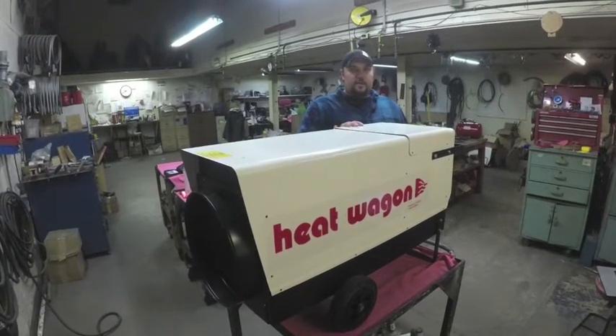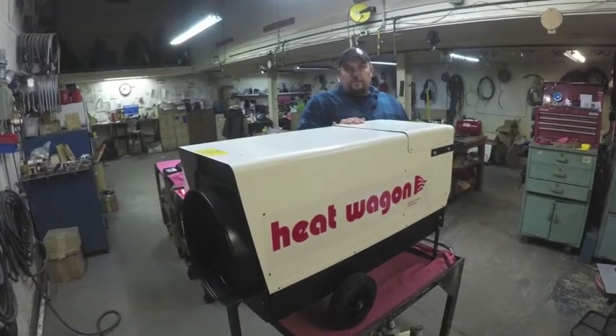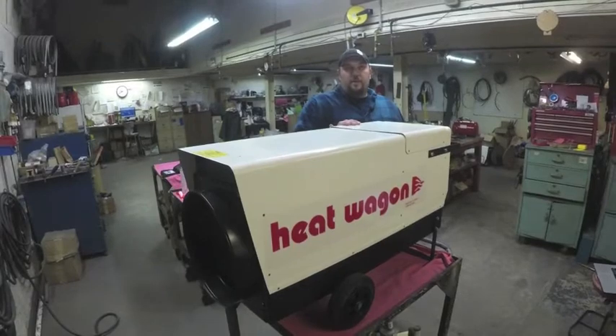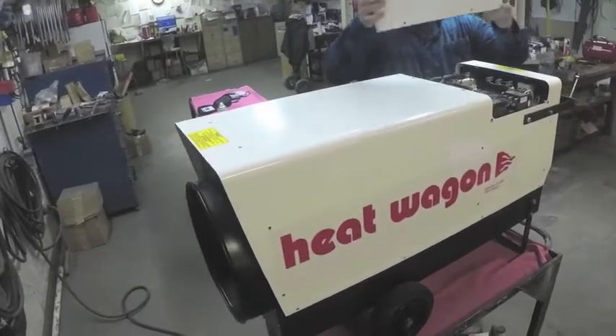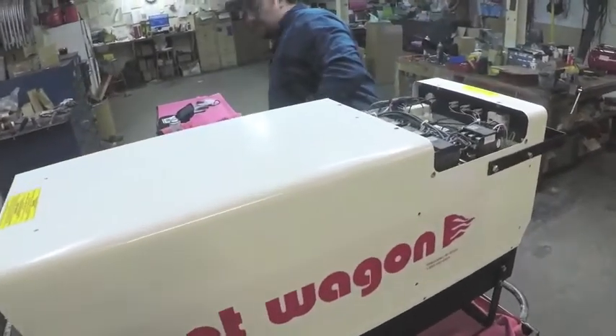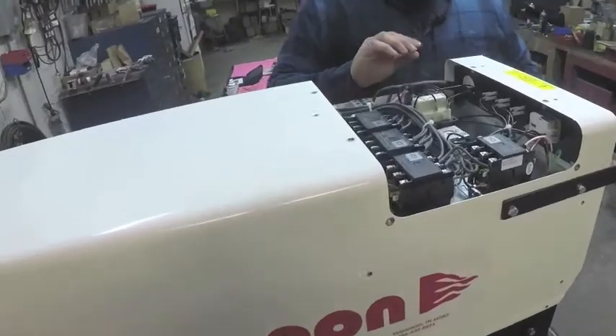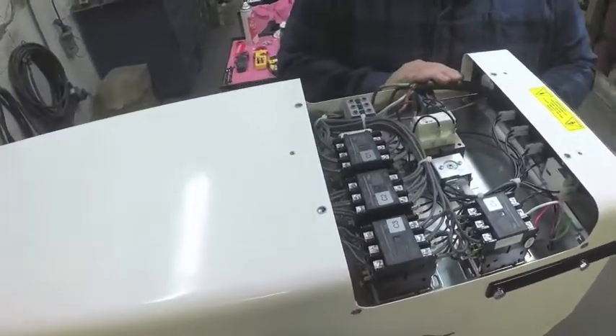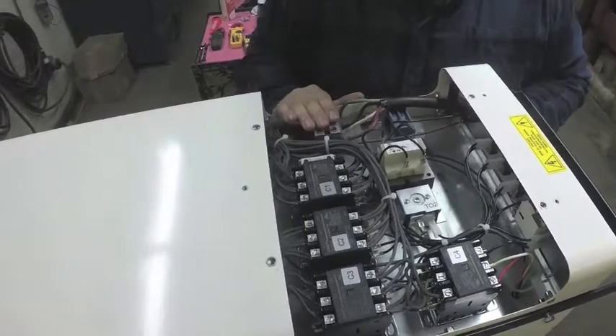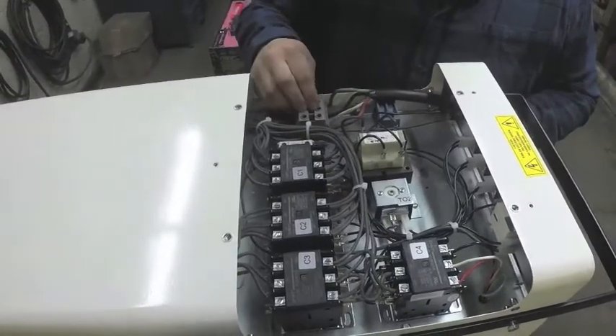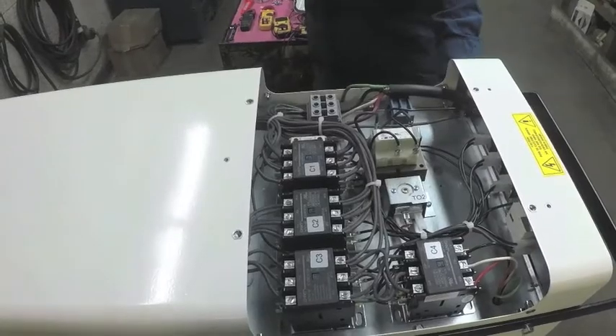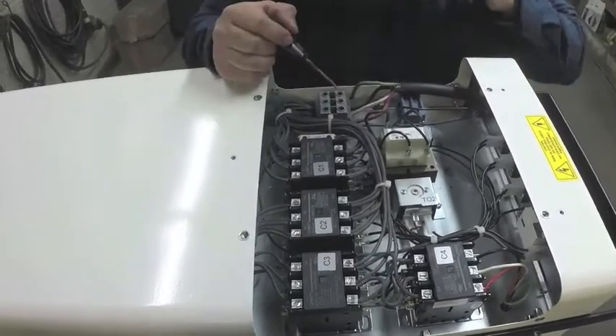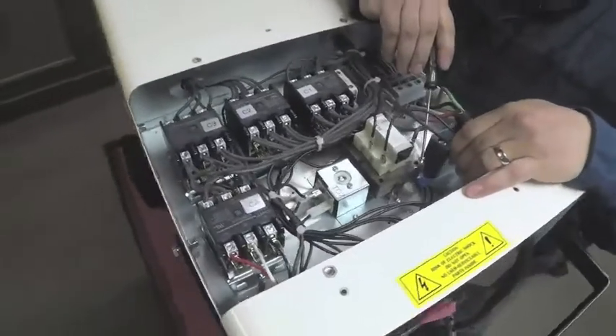We're going to be removing the cover, taking our 480 three-phase and attaching it to the terminal block. Here we can see that we have our 480 running into the input terminal block. The terminal block has hold downs for each individual lead coming in. Your ground will then go to this ground block here.